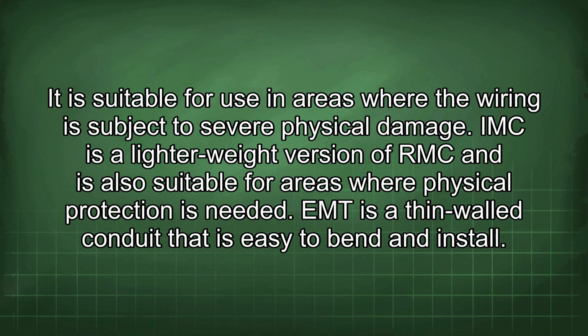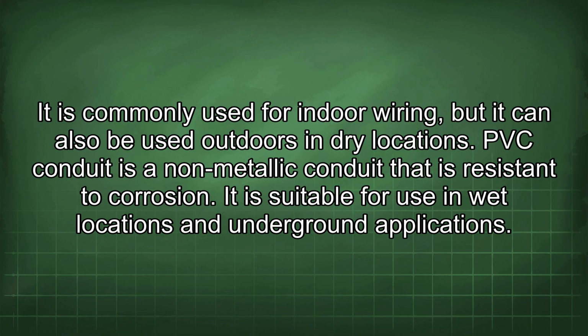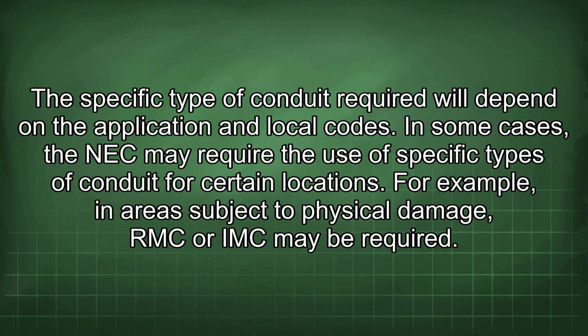EMT is a thin-walled conduit that is easy to bend and install. It is commonly used for indoor wiring, but it can also be used outdoors in dry locations. PVC conduit is a non-metallic conduit that is resistant to corrosion. It is suitable for use in wet locations and underground applications. The specific type of conduit required will depend on the application and local codes. In some cases, the NEC may require the use of specific types of conduit for certain locations. For example, in areas subject to physical damage, RMC or IMC may be required.